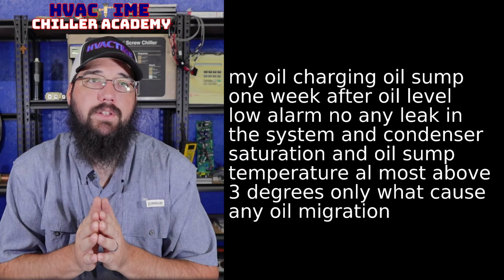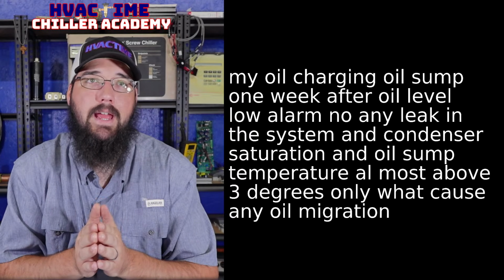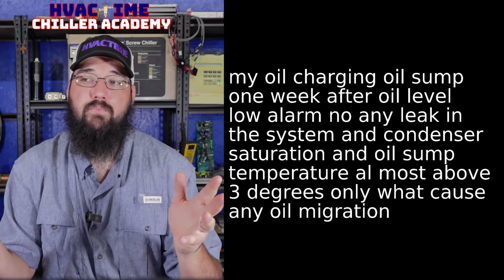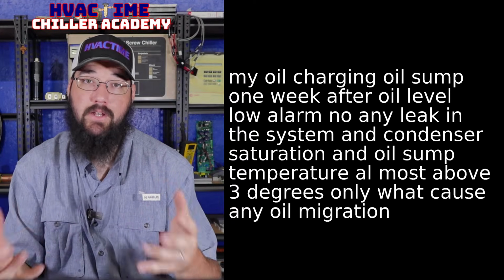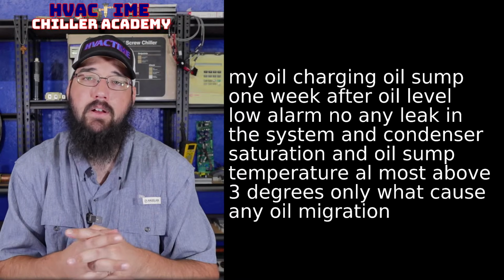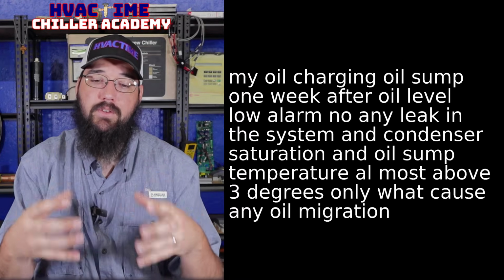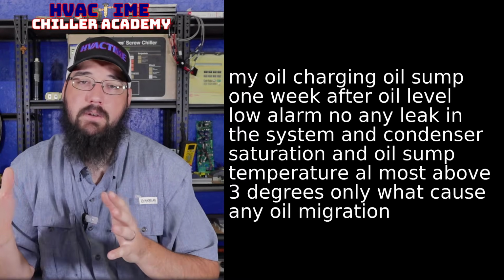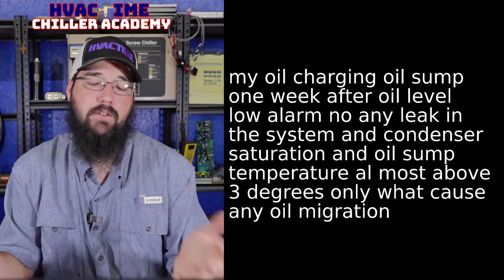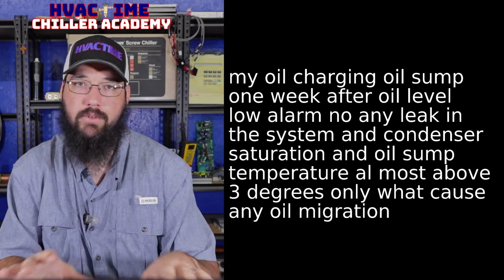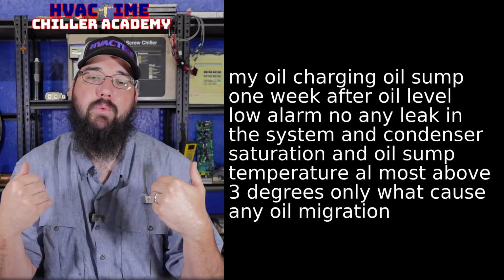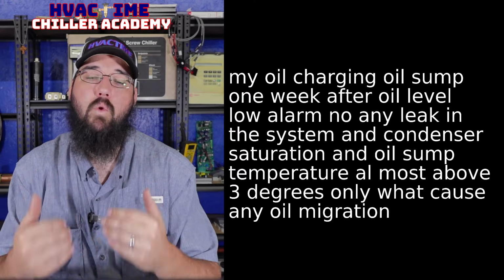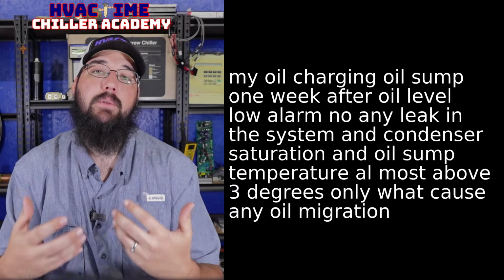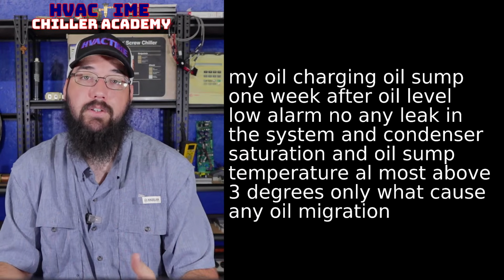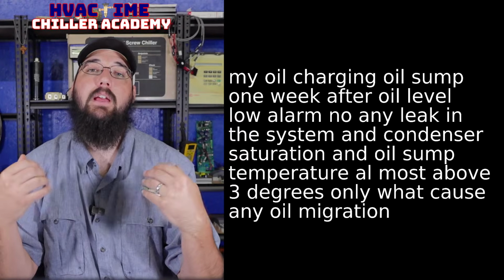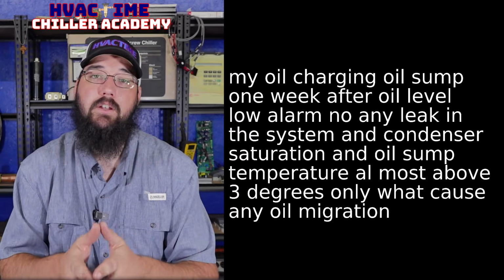I'll use a RTAC or a YVAA as two examples of why they have full circuit isolation. A YVAA has a suction isolation valve, and it's a butterfly that they put in the suction line. The whole point of that is actually to prevent a refrigerant migration freeze, which is a very different condition than oil migration. We're talking about two different things here, but the reason it became necessary, and worth it for York to put that in, is because they were having issues with migration freezes on their falling film evaps, and it was rupturing tubes in low ambient conditions.